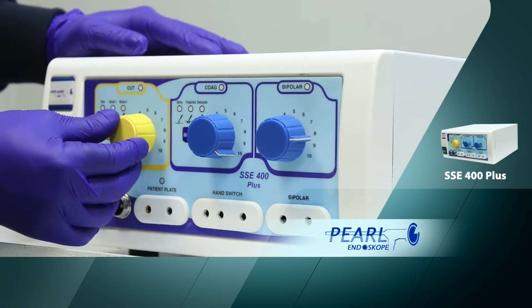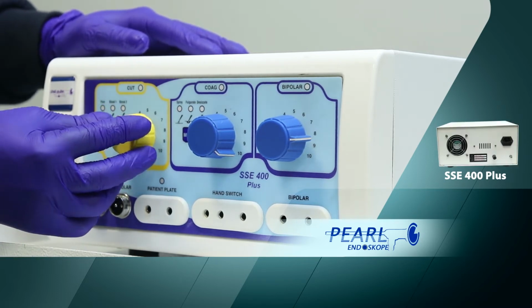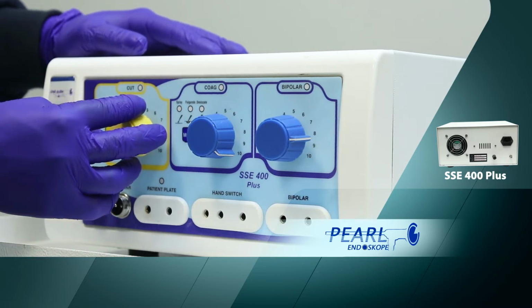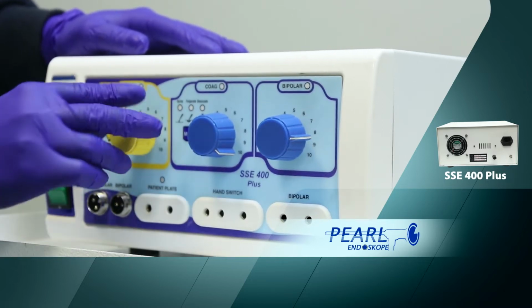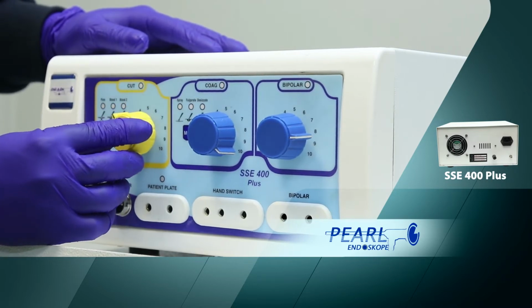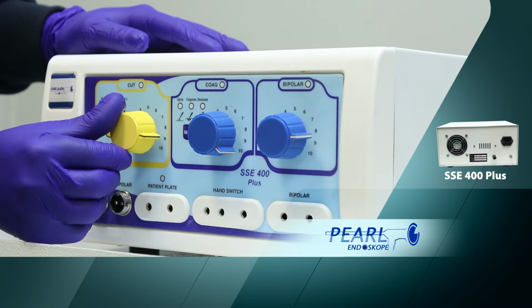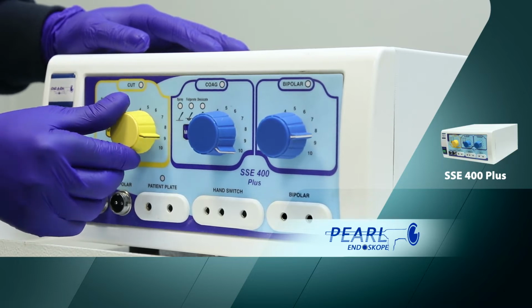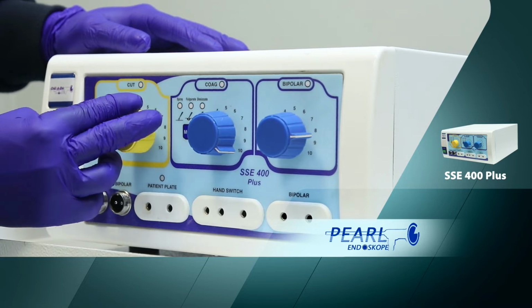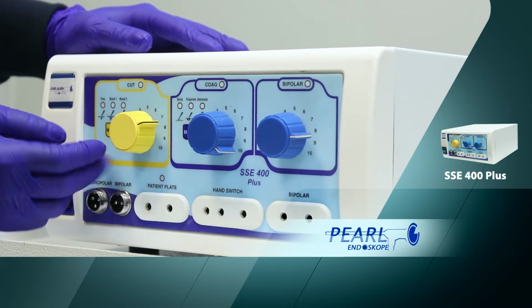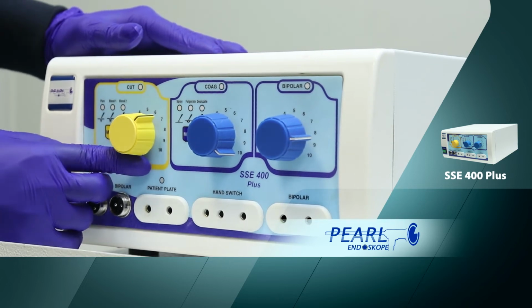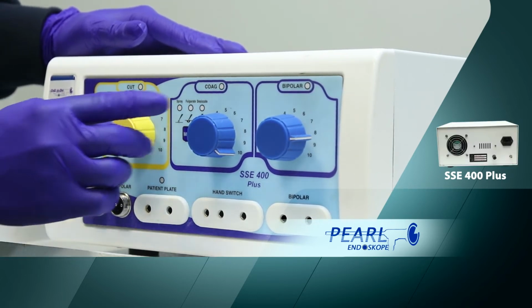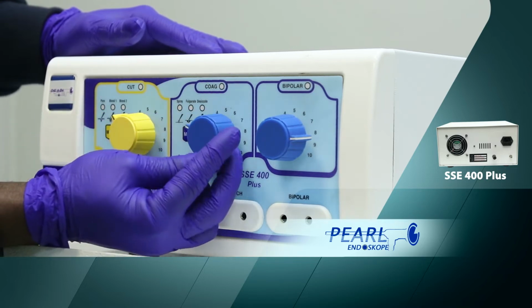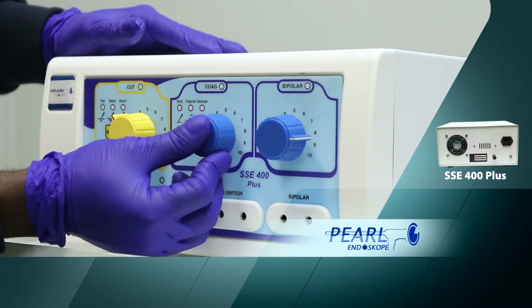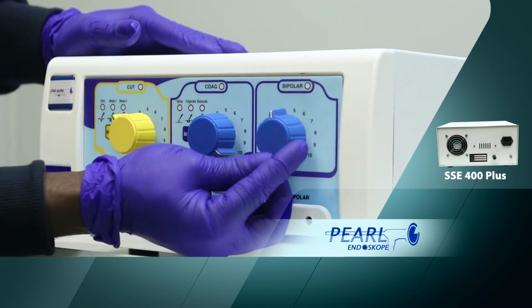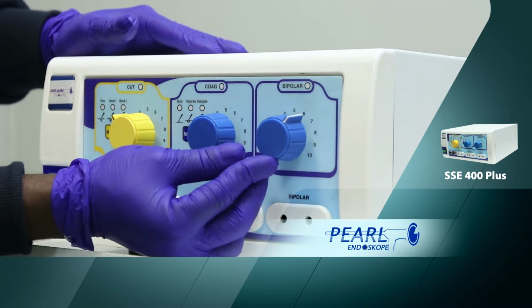This knob is to access the cut mode. The knob can be rotated clockwise for increasing the cut or anti-clockwise for decreasing the cut. It's marked from 0 to 10, can be adjusted as per required. This is the coagulation knob, calibrated from 0 to 10, and this is the bipolar knob, which is calibrated from 0 to 10.